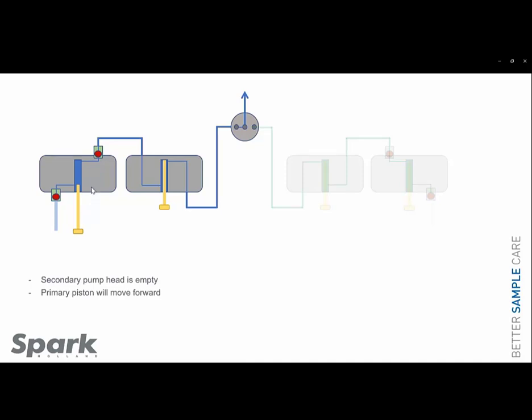Now the primary pump head will move forward. Moving the primary pump head piston forward will increase the pressure in the primary pump head. The outlet check valve will open. The primary piston will now refill the secondary pump head. At the same time, the primary pump head will also deliver the system flow rate.